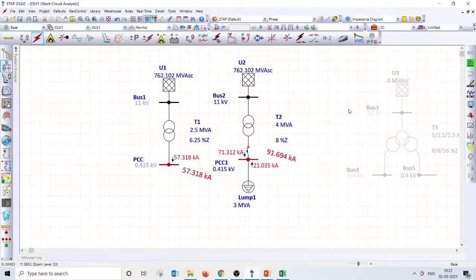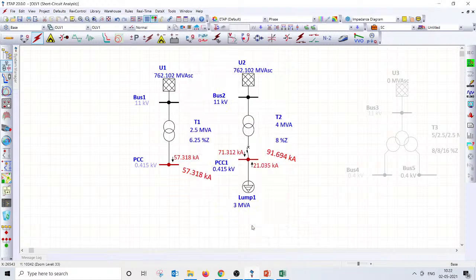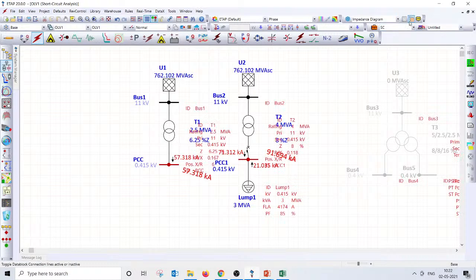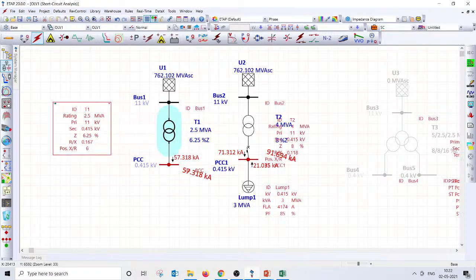Rather than wasting our time on an ETAP tip separately, we can go with the ETAP tip now itself. For example, if I want to display the X by R ratio of the transformer, which may not be possible from here. If you look at the transformer, you can display the ID, the rating, the voltage, the tap, the winding configuration, and the impedance. You cannot display anything else. But you can use this option called data blocks, and you can display whatever you want, either R by X or X by R.